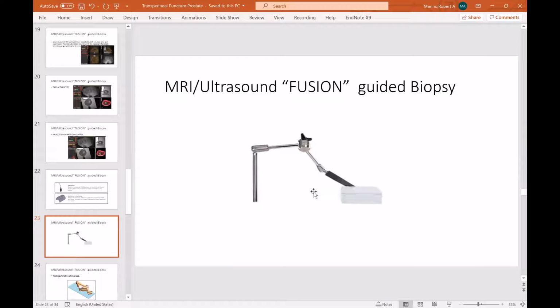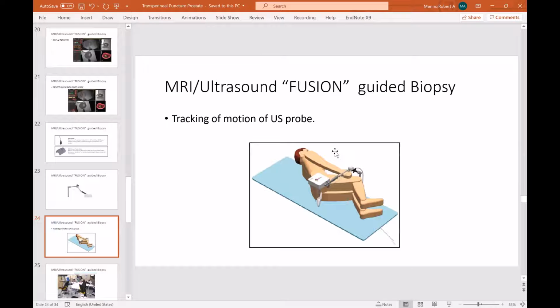This is the field generator. It's a square piece of equipment, and for our equipment it gets fixed, in this case, to the table where the patient is lying, and it's ideal to have the sensor or the transponder a little bit in the center of this box. So this is the position that is used by us most, and that I see Philips also puts out in their manual. And here's the field generator, here's the prostate probe, the patient's on their side.